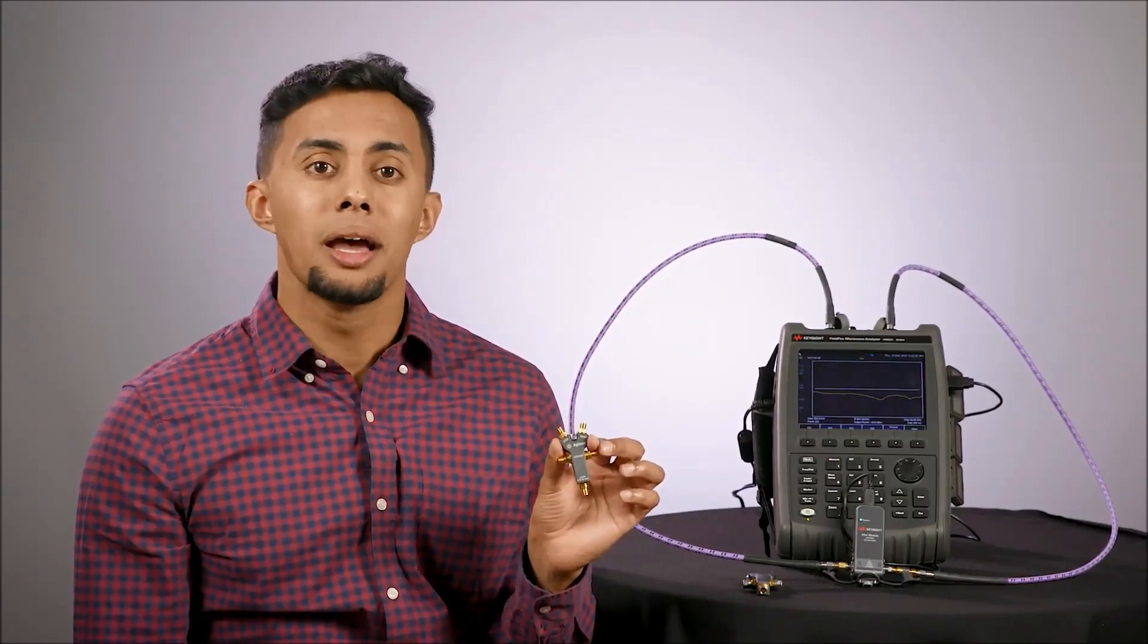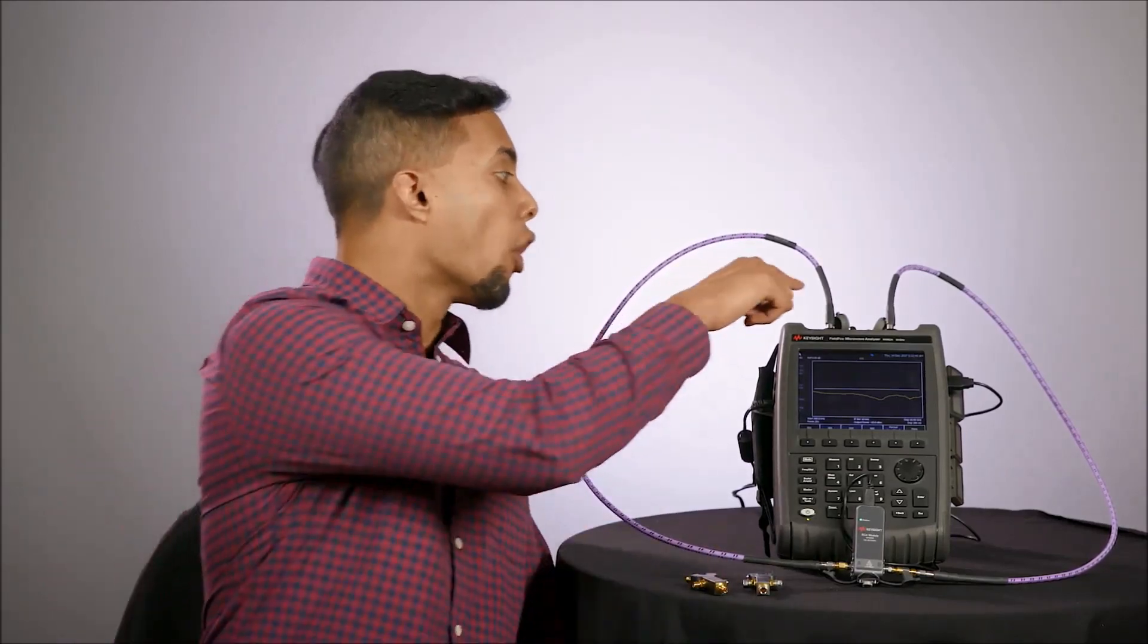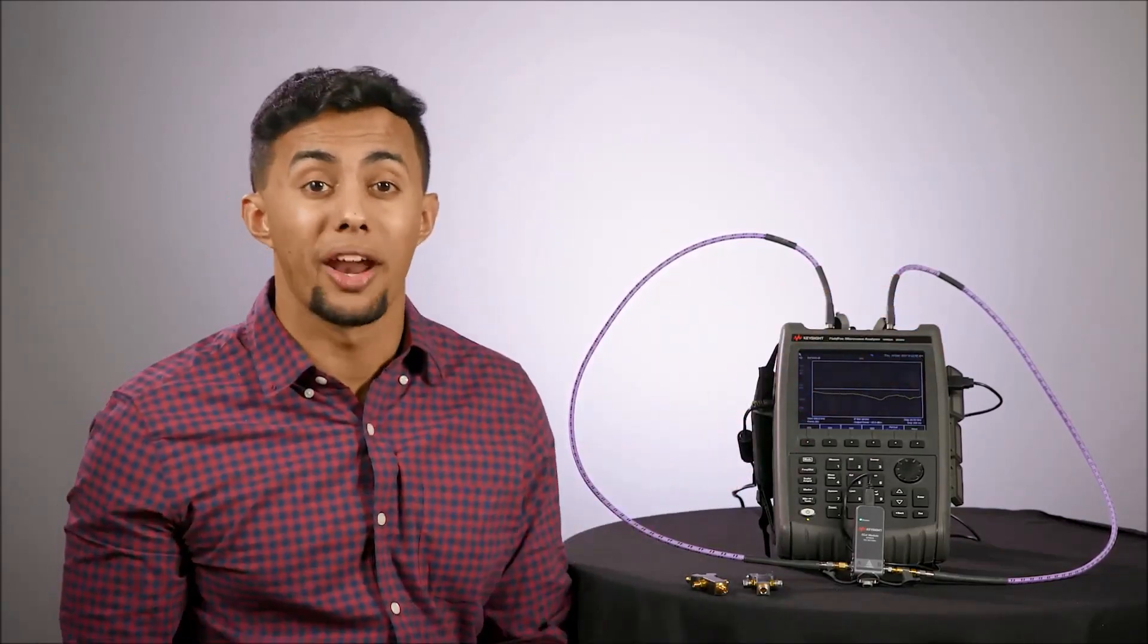Full two port calibration process requires seven connections: open, load, and short at port one and port two, and a through connection between ports one and two, which means connecting and disconnecting seven times. You get the point. This takes a lot of time.